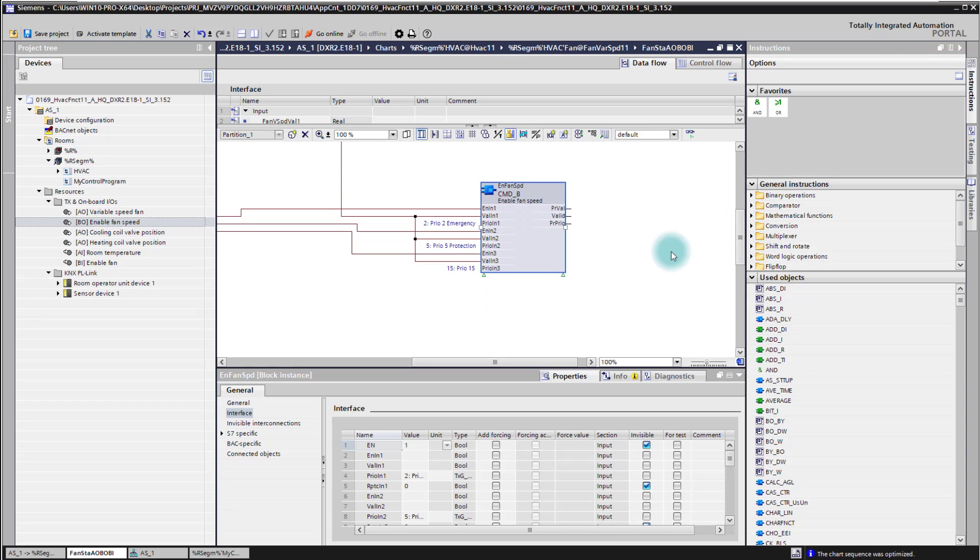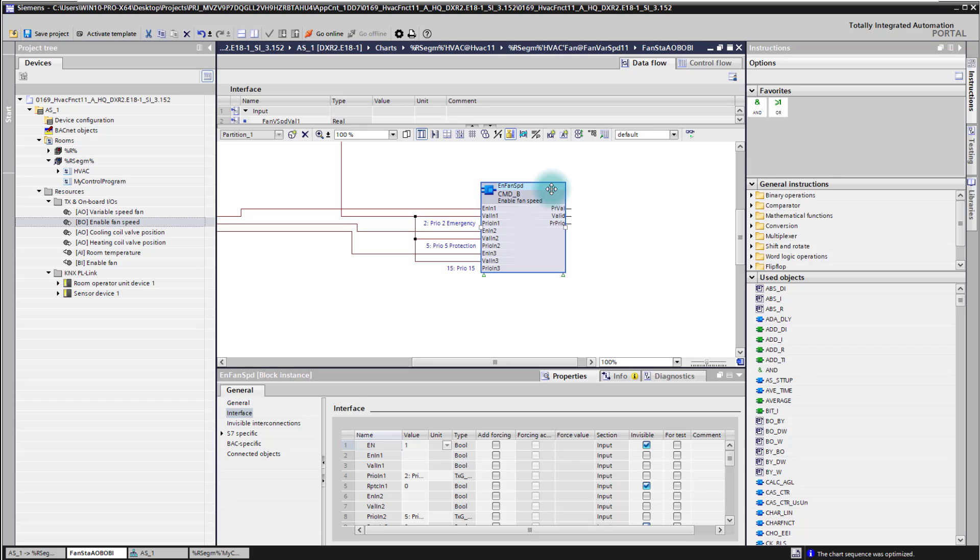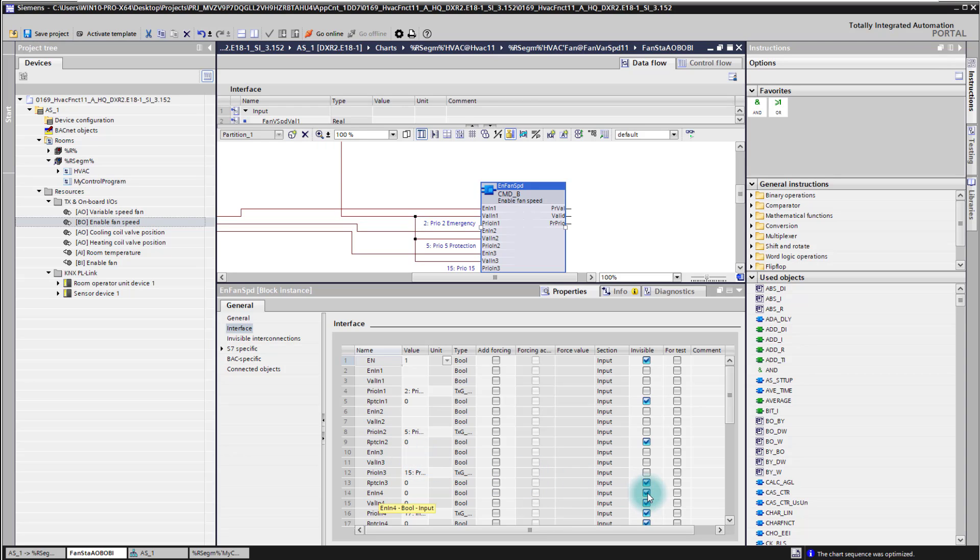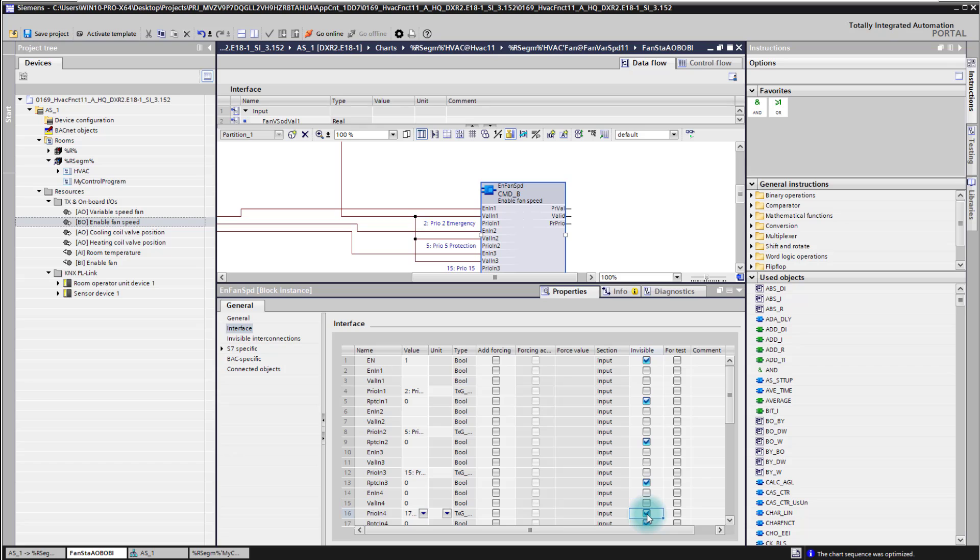Now how to connect the input directly with that output block. For this we need first to enable here more inputs. We can simply do so by selecting the block. And then in the properties of that block we see here the interfaces. Here we have a list of all the interfaces. As you can see interface 1 to 3 is used already but interface 4 is still available. With unchecking here the box they are getting visible in our CFC plan.